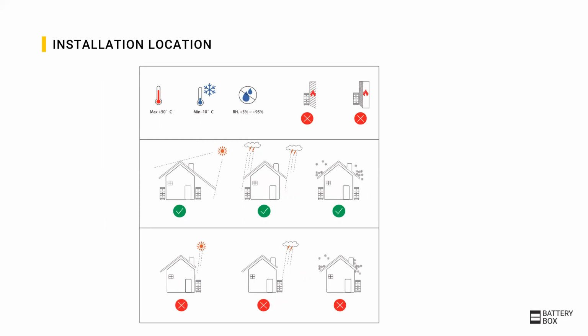Here you see the requirements for the installation location. The temperature range is from -10 degrees to +50 degrees. The battery can operate within this temperature range, however, the power will be slightly limited below 0 degrees. The battery should not be placed close to easily inflammable materials.